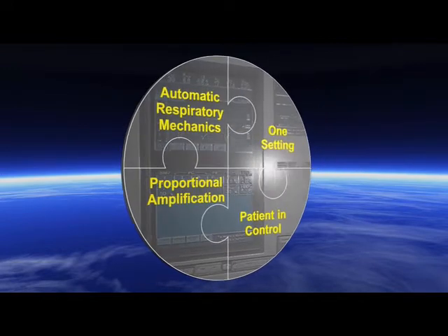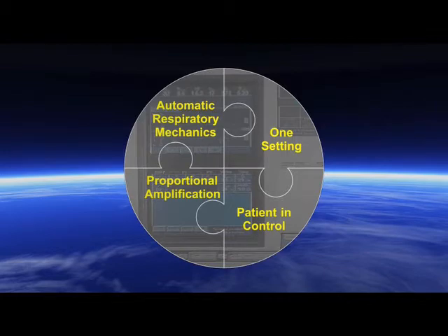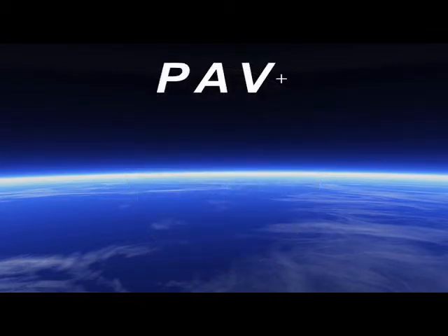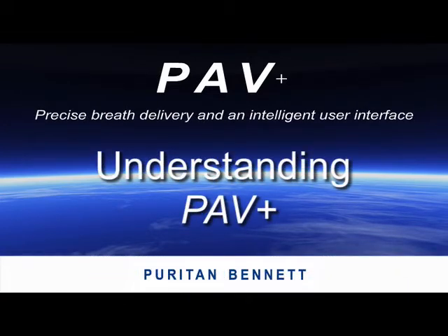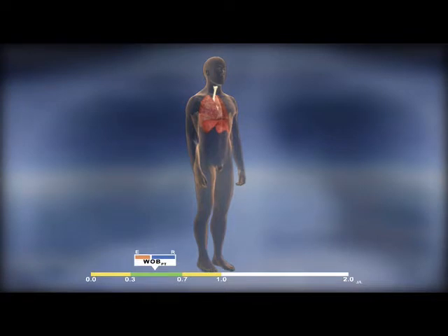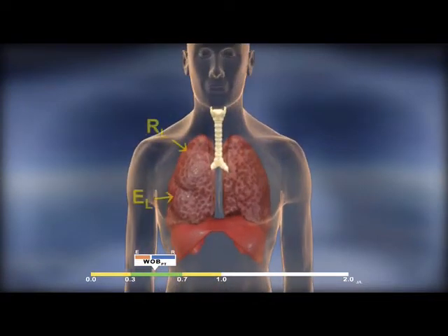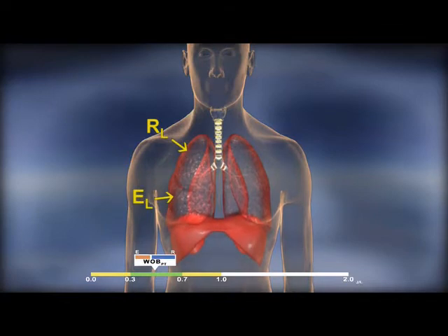Percent support is your primary setting. To understand PAV Plus, we must first understand some of the physiology behind normal respiration. When we take a breath, the diaphragm must work to overcome a couple of specific forces — the elastic and resistance forces of the lungs and thorax. PAV Plus will uniquely monitor changes in elastance and resistance by performing automated random measurements every four to ten breaths. These measurements are used in the breath delivery strategy of PAV Plus.